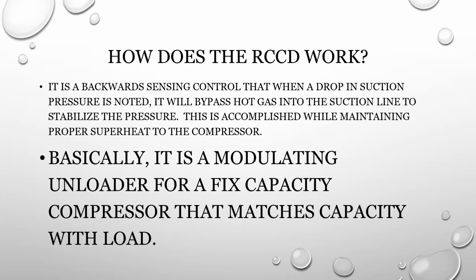The RCCD control is a backward sensing control device that when a drop in suction pressure is noted, it will bypass hot gas into the suction line to stabilize the pressure. This is accomplished while maintaining proper superheat to the compressor.